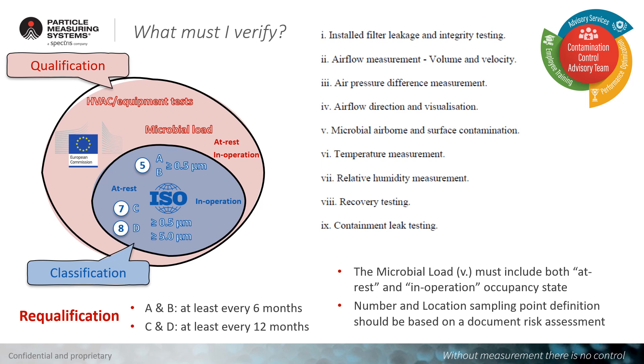Another important clarification of this draft is about requalification, which must be executed at least every six months for grades A and B, and at least every year for the other grades. The new draft also specifies the tests needed and after which changes or extraordinary events we must re-qualify a clean room.